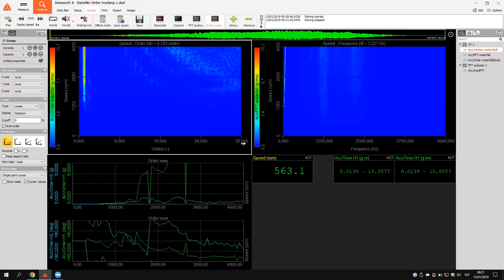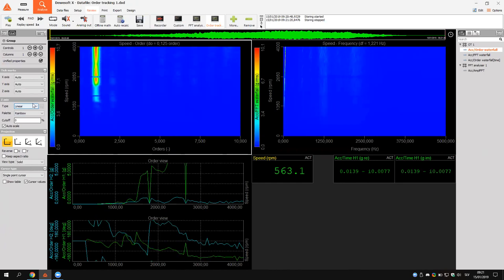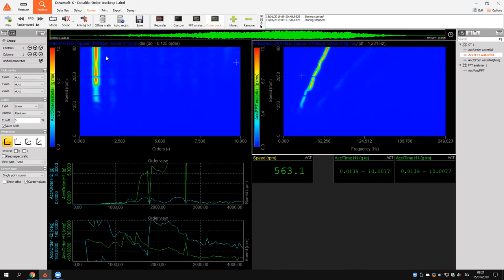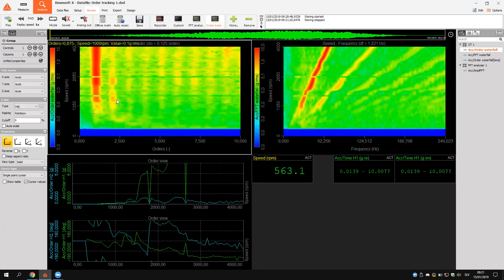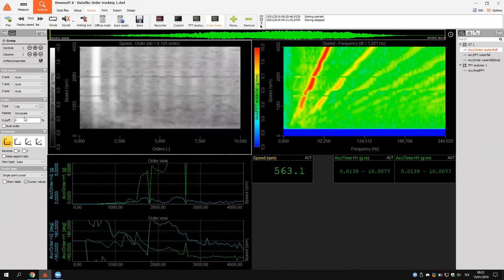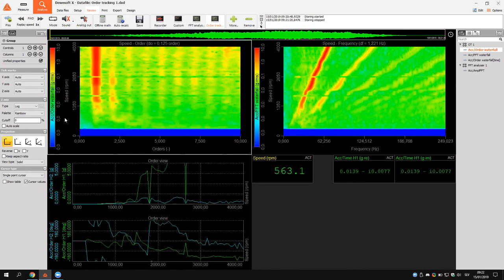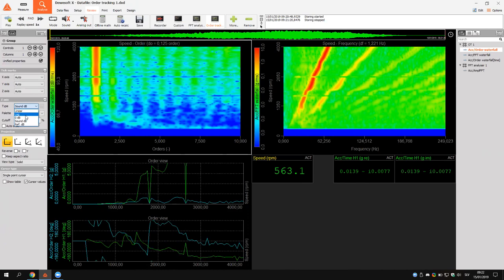In analyze mode, for example I want to see the order waterfall up to the 10th order. I can select the display type — currently linear — and I can see that the first order is really the strongest one, meaning I have a strong unbalance in my machine. I can also change to logarithmic scale to see the other orders more clearly, and I can change the color of the graph. If measuring with a microphone, I can select sound dB and it will automatically convert to dB level.